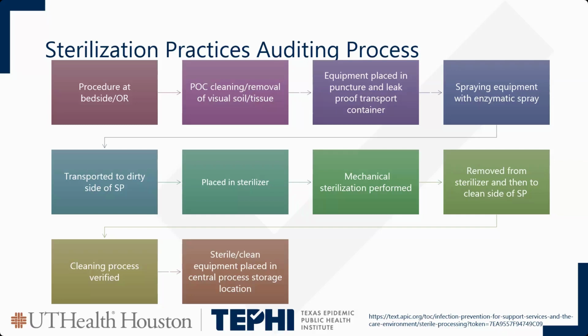So then when you're in the dirty side, you're watching them, you're talking to staff, you're asking about flow, you're asking about PPE. They know what to wear since they are handling very hazardous bio waste and they're exposed to a lot of chemicals. So you're making sure the device is being cleaned and that they are staying safe. Then once whatever device you're looking at goes into the cleaning piece of equipment, then you're leaving, which is usually on a pass-through. So the area is set up in 3 different zones, and that pass-through is kind of like a dishwasher. You put it on the dirty side, and then when it's clean, it gets opened up on the clean side. So there's not this going back and forth from a dirty to a clean zone.